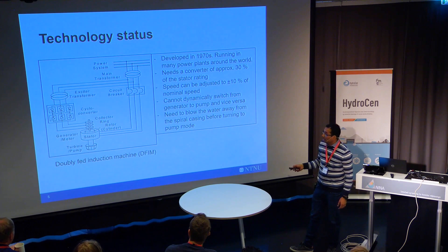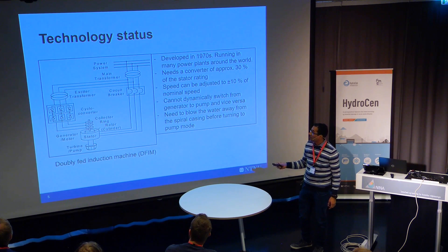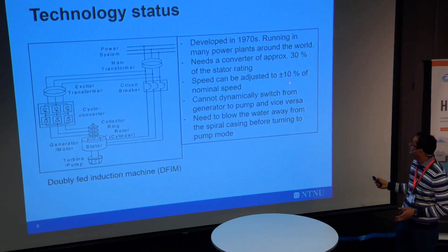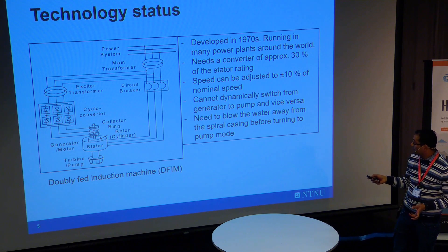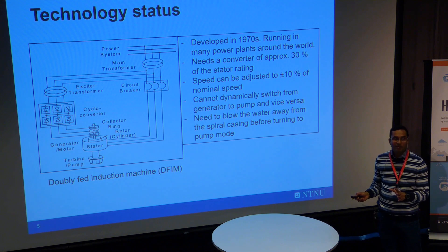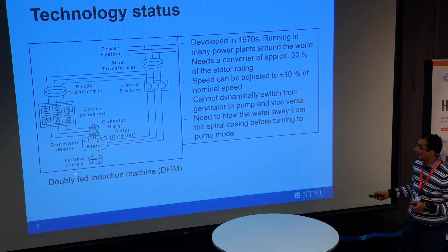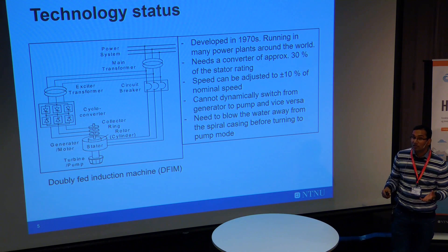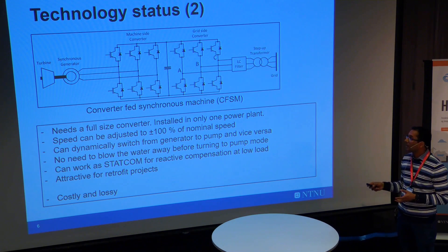This type of machine is being used to vary the speed today. As Arne was explaining, we feed power through the rotor, and we need only a very small converter — only 30% of the size — to adjust the speed by about 10% of nominal speed, which is good enough for the range of variable speed operation. But this technology has a known disadvantage: we cannot change from generation mode to pumping mode dynamically. We need to blow the water away from the spiral casing before switching modes, so we have to wait maybe 5–10 minutes.